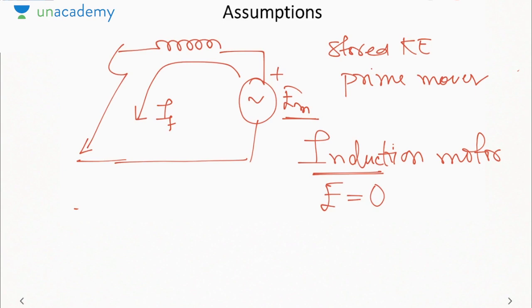Okay, so that is why we will neglect the induction motor under faulty condition, because it will not be able to supply the fault current. Only a synchronous motor can supply the fault current, not the induction machine. So we will neglect any passive loads and we will consider only the synchronous motor under faulty condition. These are certain assumptions that we will maintain, and in case of a generator we will assume that synchronous speed is constant, so that frequency is also constant under faulty condition.